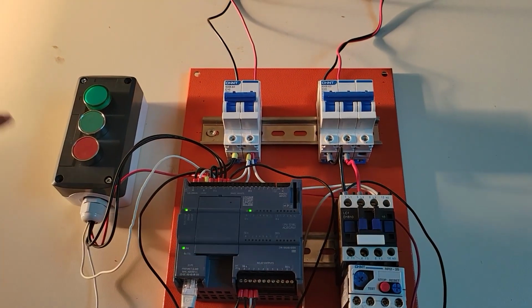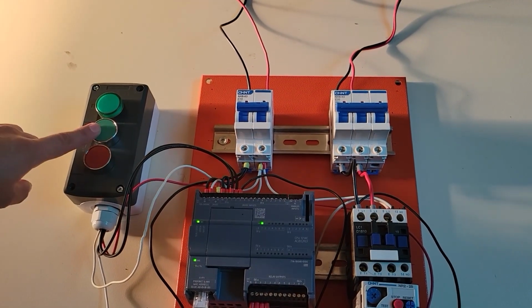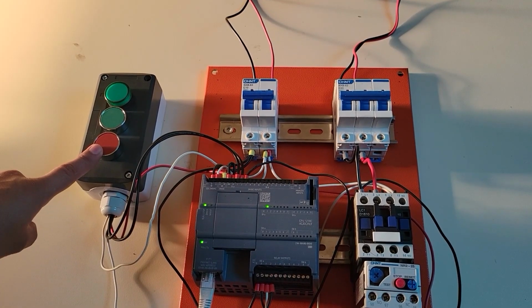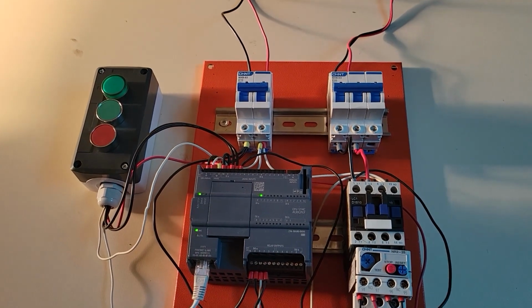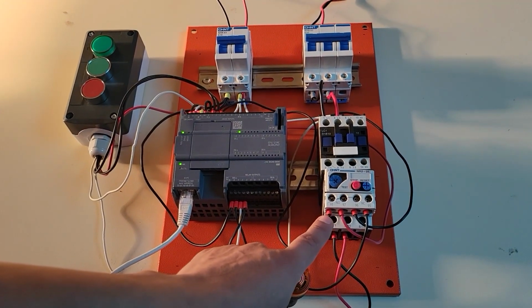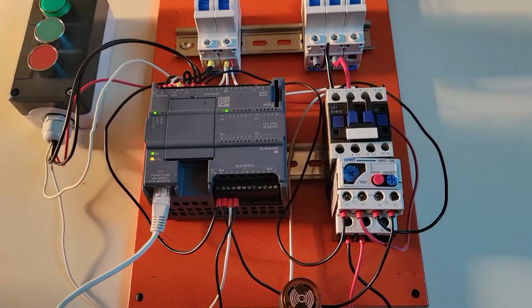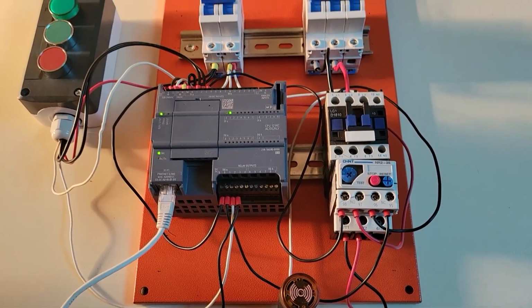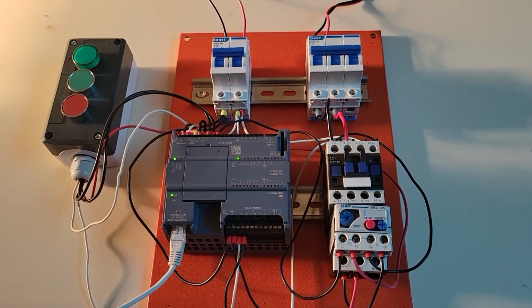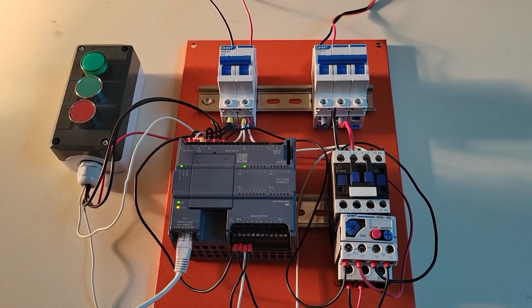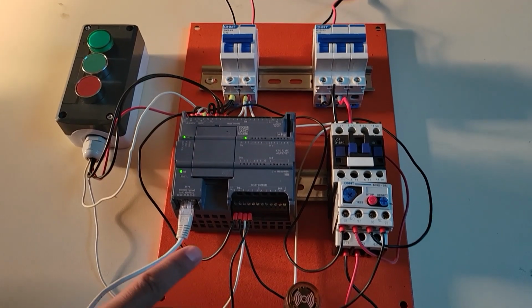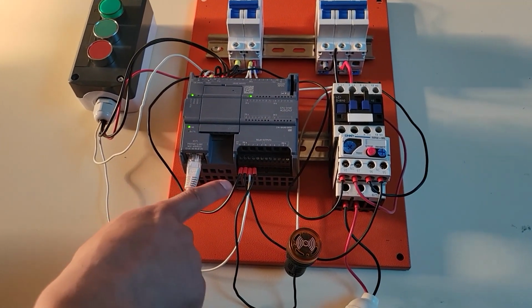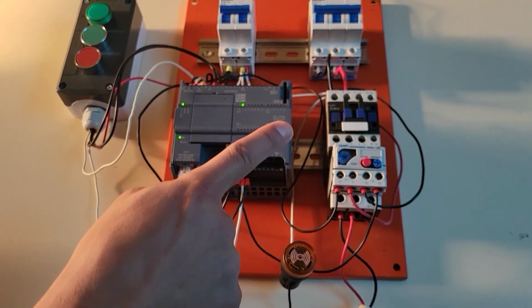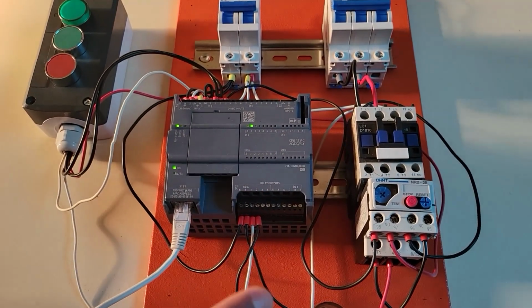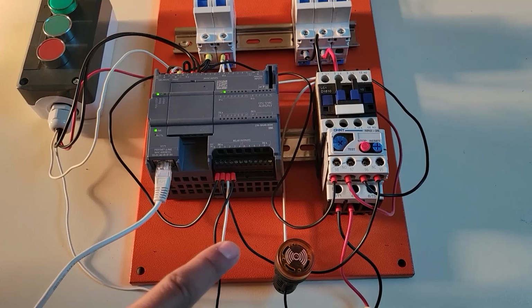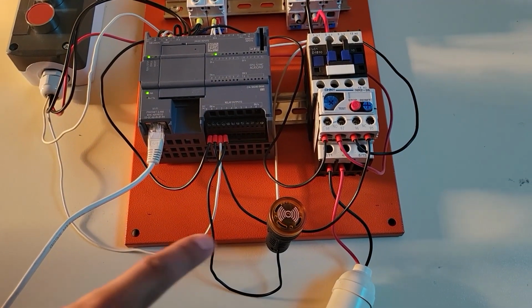We have 3 inputs to the PLC. The start button, the stop button that are in this box next to the start indicator. The 3rd input is sent from the normally open contact of the thermal relay. We also have 3 outputs connected to the PLC. The 1st output is connected to the closed contact of the thermal relay and then to the contactor. The 2nd output is connected to the on-off indicator light. And the 3rd output is connected to the overload fault indicator light.